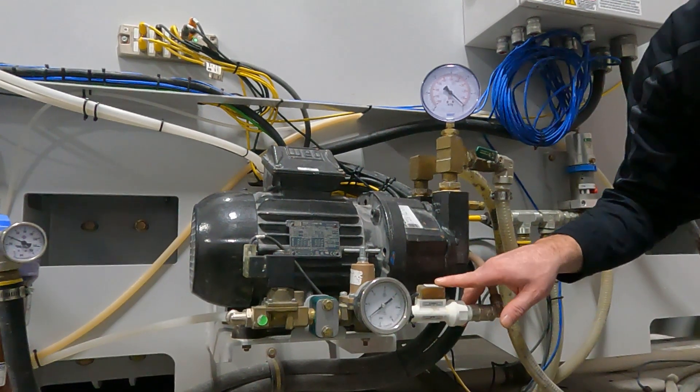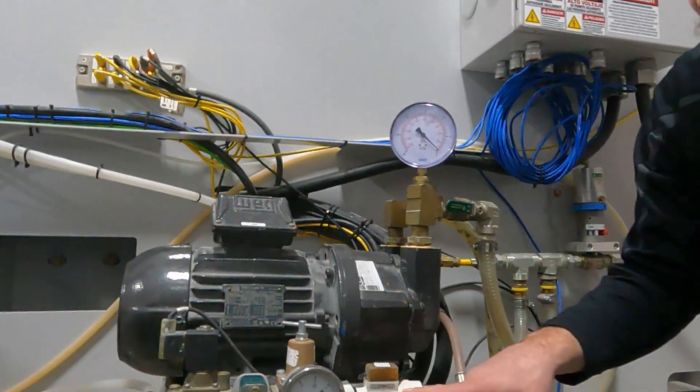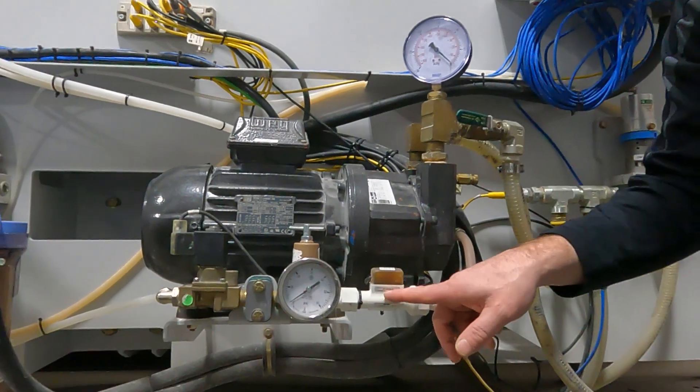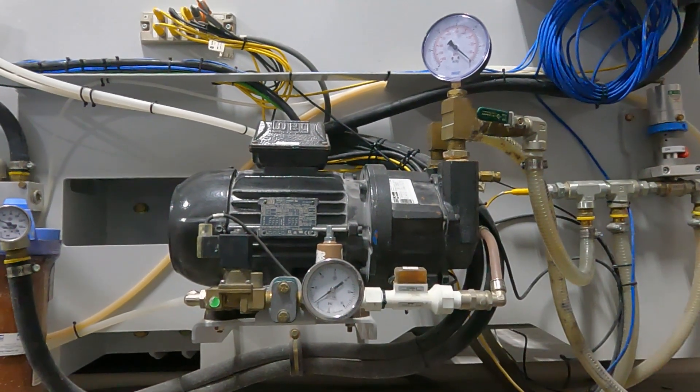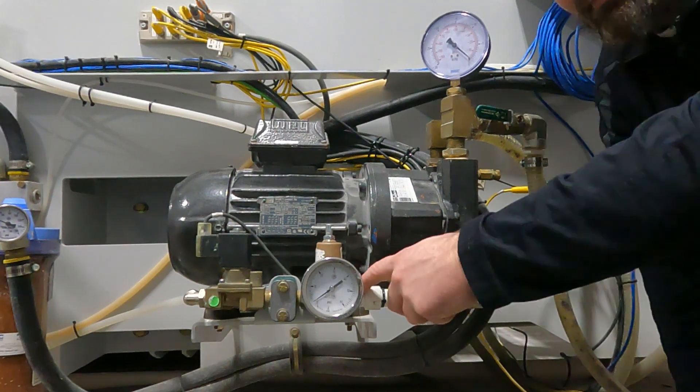Now here's our vacuum pump flow switch. This is what's telling us we have no flow. We can take this out also and clean that up if we have good water flow all the way up to this.